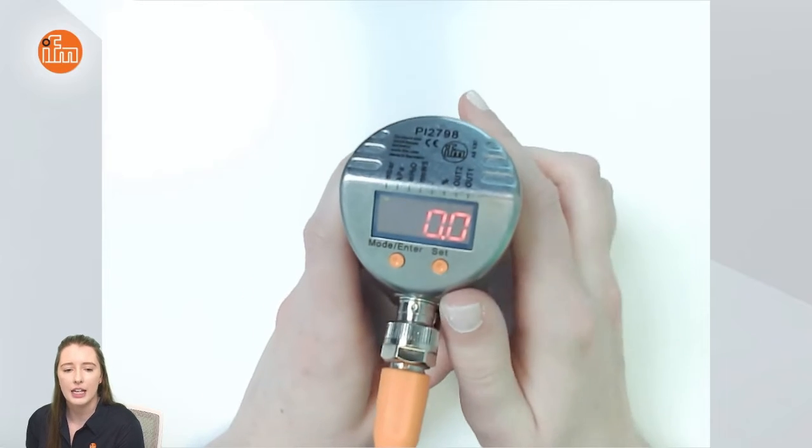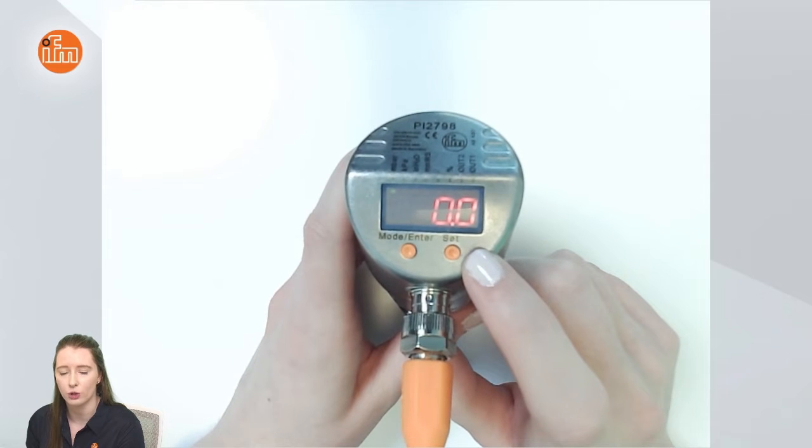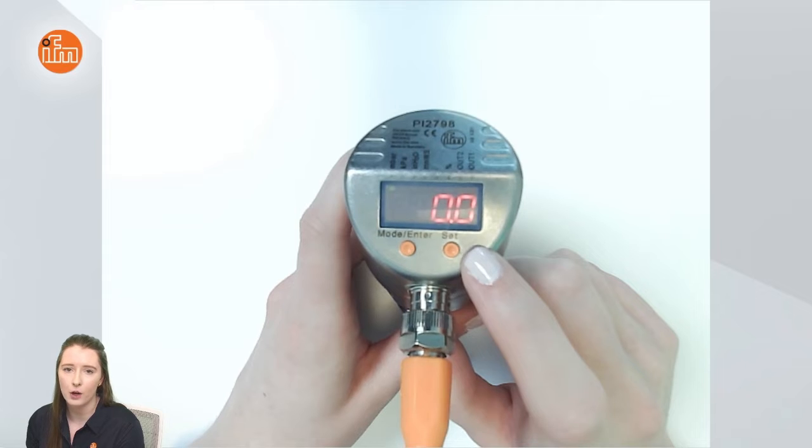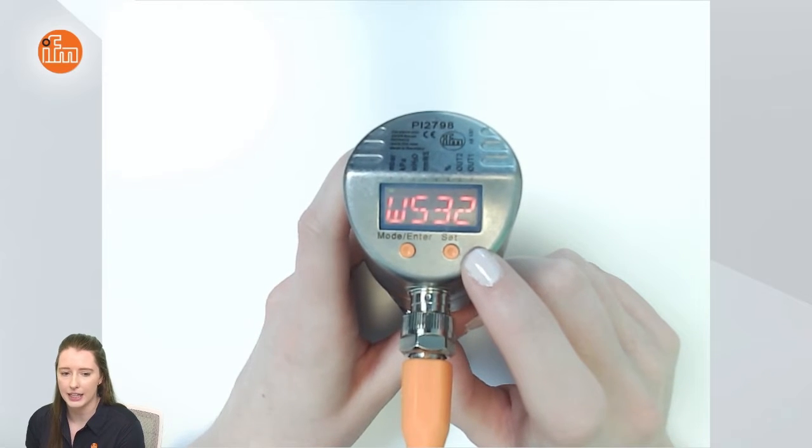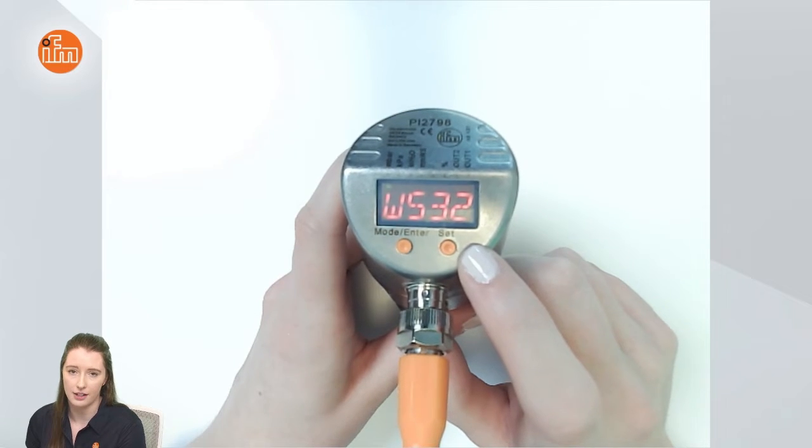Before I do this I need to mention that this unit is currently displaying the W532 error because output 2 is factory set for an analog output and right now I have the output 2 wire not connected to anything. To get this error away you would connect output 2 to some type of load or you would change the output 2 parameter to a switching output instead of an analog output.